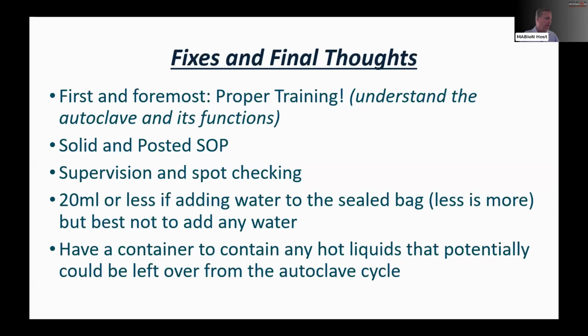So you're asking about the effluent from an autoclave being potentially infectious when that vacuum is pulled. The effluent liquids, when you're pulling it out, that's pretty much going down the drain. If it's highly infectious, you should have an EDS system, especially if you are in a BSL lab. All that should literally be going down to EDS and being treated.